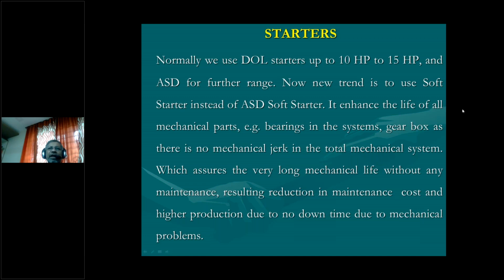So now the next target is zero maintenance. Zero maintenance regarding electrical and all the things, but regarding mechanical, if you control the prime mover's action, yes, you can go for zero maintenance of mechanicals also. Now, in case of drives for particular conveyor operations, if you want to control the speed or the feeding, yes, by means of a drive. Every fan, your pumps, your conveyors are very good opportunities for VFDs. Then mechanical equipment having a gearbox is a good opportunity to use soft starters.